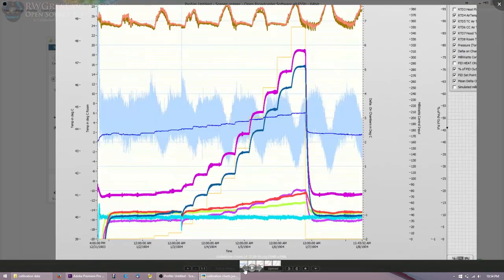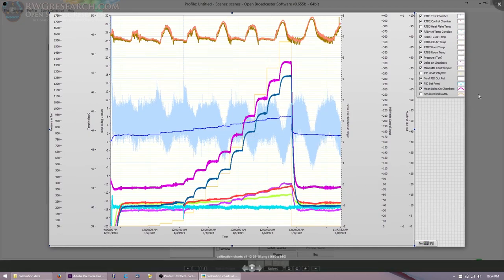So, here is an overview where you can get to see this true error tolerance. So, this was basically almost a day. Not quite two days here. About a day and a half. And you can see our little bit of error tolerance that I was referring to. I was putting no heat in here. But yet, I was seeing a difference in potential between these two chambers. So, that's 0.19, not even quite. About 0.195 to about 0.17. Alright. So, that's my roughly 0.02 degrees Celsius error tolerance. So, pretty small. And then the last graph here just shows sort of an overview of the system again. So, there you go. That is my calibration data. And I hope that made sense to you. So, let's continue the video.